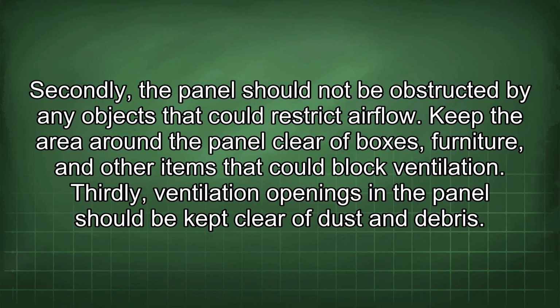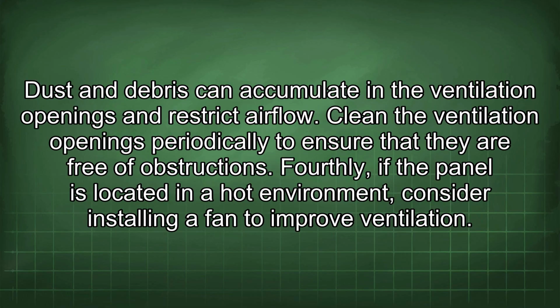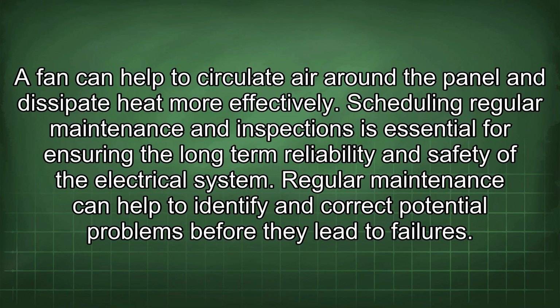Secondly, the panel should not be obstructed by any objects that could restrict airflow. Keep the area around the panel clear of boxes, furniture, and other items that could block ventilation. Thirdly, ventilation openings in the panel should be kept clear of dust and debris. Dust and debris can accumulate in the ventilation openings and restrict airflow. Clean the ventilation openings periodically to ensure that they are free of obstructions. Fourthly, if the panel is located in a hot environment, consider installing a fan to improve ventilation. A fan can help to circulate air around the panel and dissipate heat more effectively.